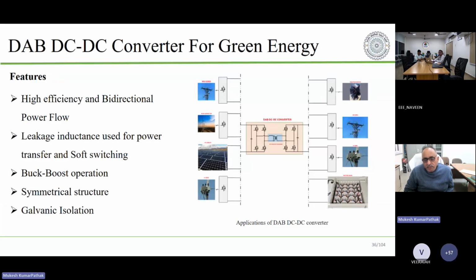But suppose, because of renewable energy penetration, the converter rating now needs to handle powers in hundreds of kilowatts and even megawatts. If the power rating is 500 kilowatts and efficiency is 90%, that means 50 kilowatts is the loss. This loss of 50 kilowatts, as far as power is concerned, is a huge loss. Whatever kind of system you have, if a loss of 50 kilowatts is taking place continuously, it is something we should be worried about. Also, any converter creating a loss of 50 kilowatts, that loss dissipation itself will become a problem.